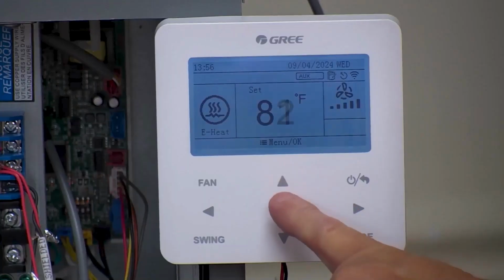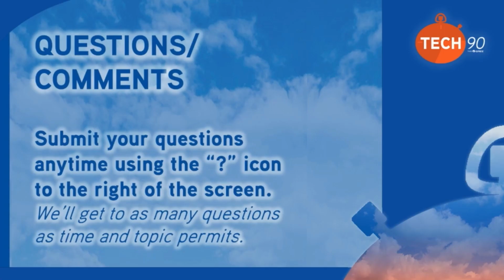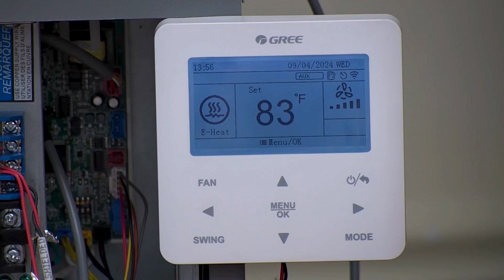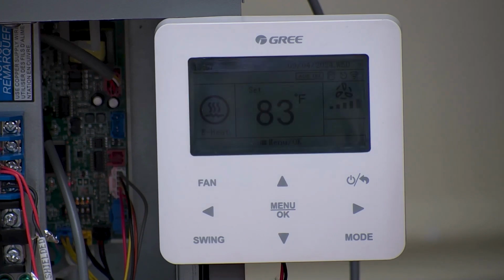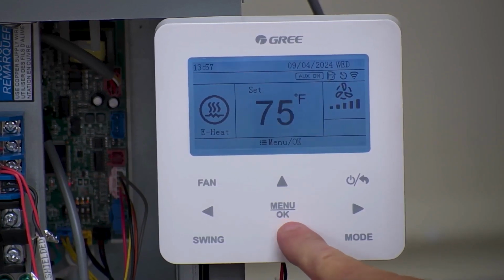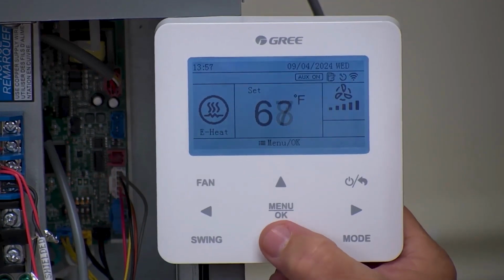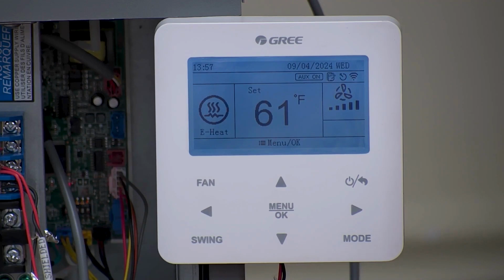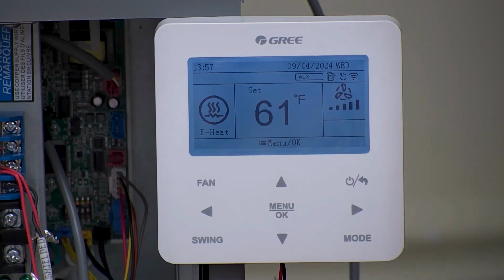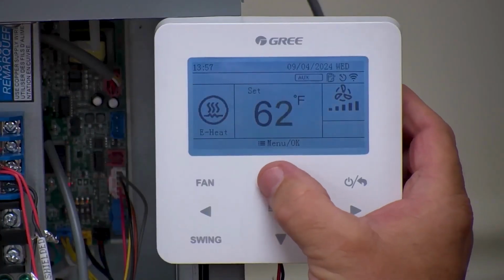So now I can crank this up, and I should be able to get my electric heat to come on. There it goes. In a minute here, I should see amp draw. There we go. So about 19 amps. We're on 208, so it's going to be 18, 19 amps. Then if I run my temperature down, I should be able to get it to cycle off. And it also says right up here at the top, it just says aux on. So whenever the electric heat's running, whether it's eHeat or auxiliary heat, it will tell you the aux is on. I'll show you that one more time. Let me turn it back on.